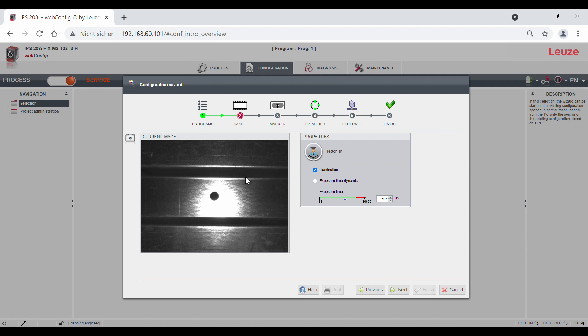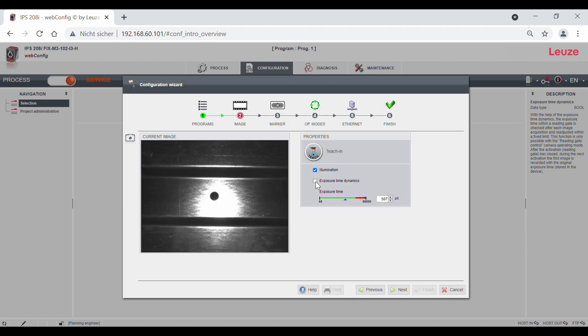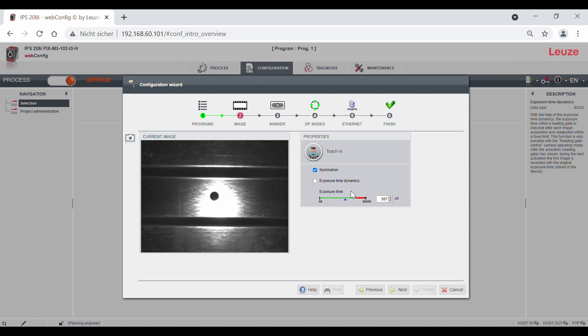The checkbox exposure time dynamics affects the control of the sensor in the process mode in the reading gate control mode. With exposure time dynamics, the contrast in the center is checked during a reading gate after each image acquisition and readjusted if necessary. Now we have a sufficiently good contrast.